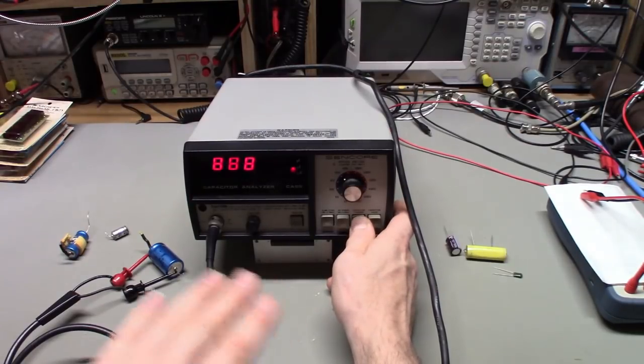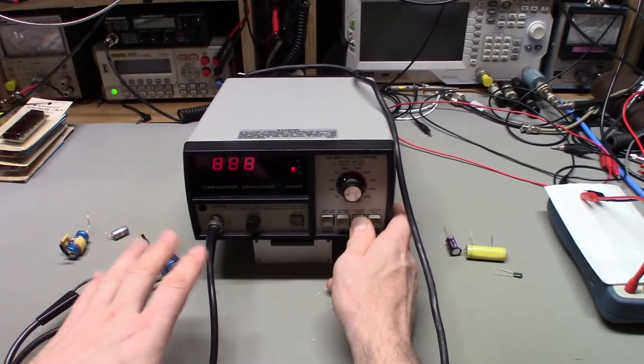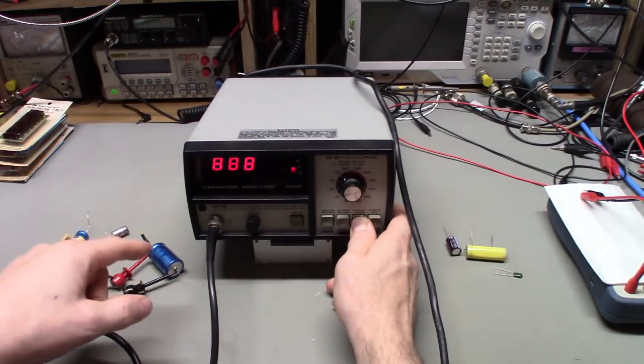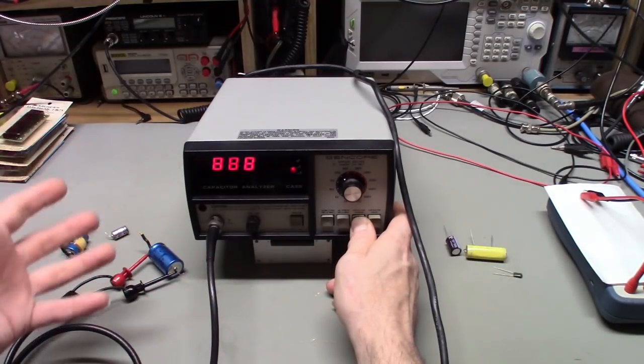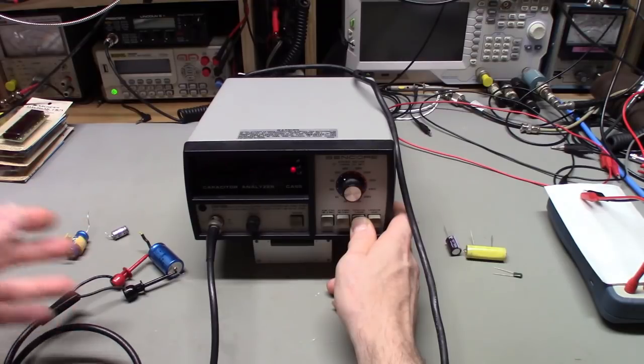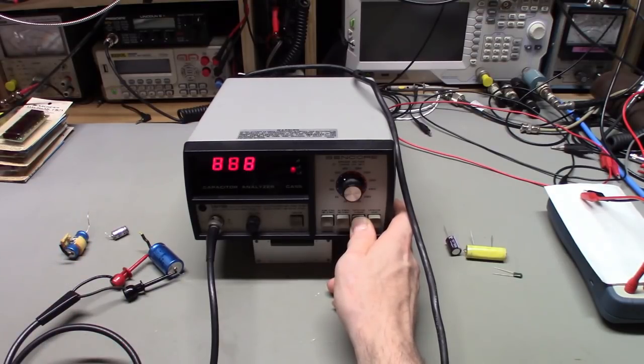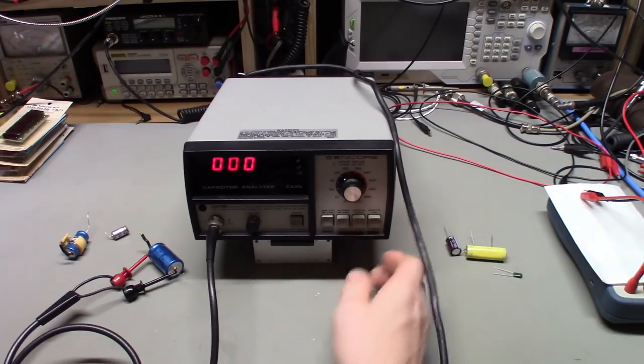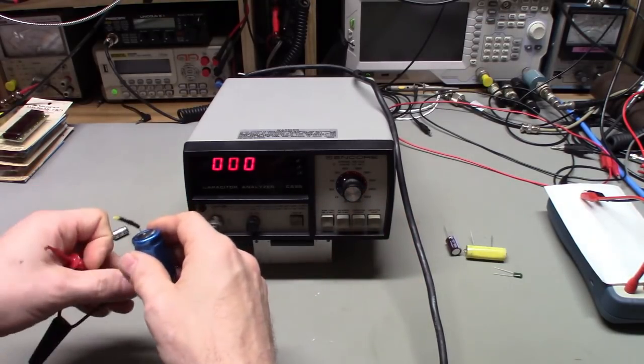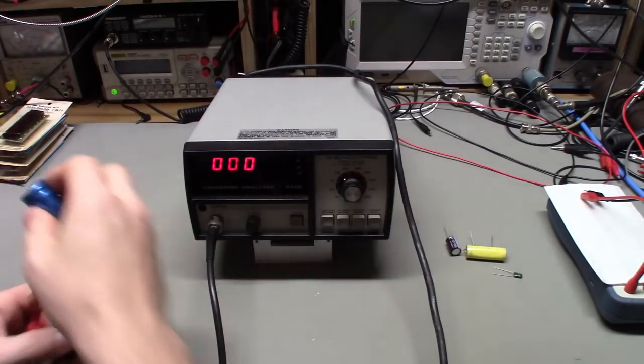That's something else you'll find with electrolytic capacitors when you're doing tests, because the capacitor has to charge up. So it's going to be drawing an excessive amount of current while it's charging. But this one's just not charging, because it's just not coming off the flashing display. So that one exceeds 10,000 microamps of leakage current. Definitely a bad cap. Like I say, we can just look at it and see it's bad.